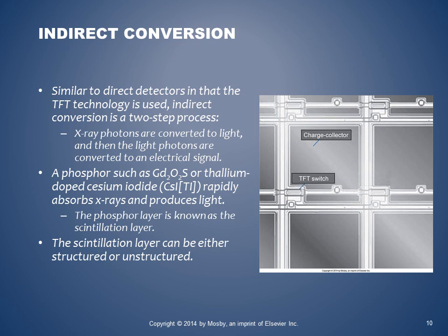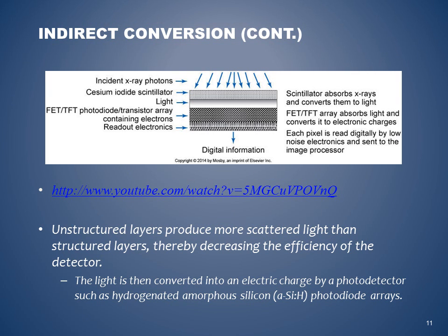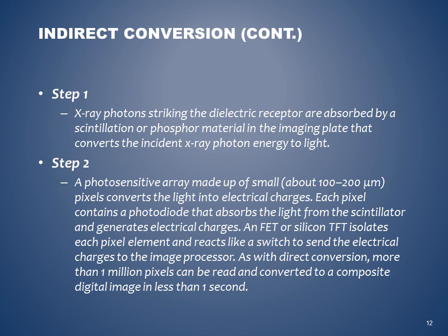The scintillation layer can be either structured or unstructured. Unstructured layers produce more scattered light than structured layers, thereby decreasing the efficiency of the detector. The light is then converted into electronic charge by a photodetector, such as hydrogenated amorphous silicon photodiode arrays. Indirect conversion. Step 1. X-ray photons striking the dielectric receptor are absorbed by a scintillator or phosphor material in the imaging plate that converts the incident X-ray photon to light. Step 2. A photosensitive array made up of small, about 100 to 200 micron pixels converts the light into electronic charges.